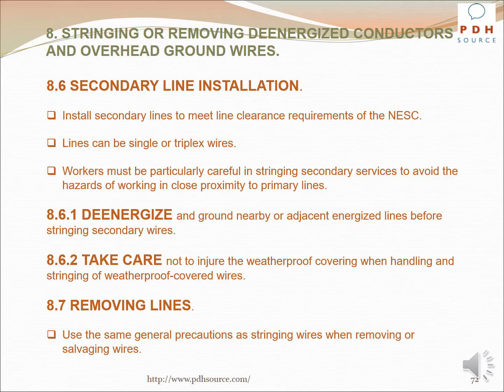With regard to secondary line installation, install secondary lines to meet line clearance requirements of the NESC. Lines can be single or triplex wires. Workers must be particularly careful in stringing secondary services to avoid the hazards of working in close proximity to primary lines. De-energize and ground nearby or adjacent energized lines before stringing secondary wires. Take care not to injure the weatherproof covering when handling and stringing of weatherproof covered wires.